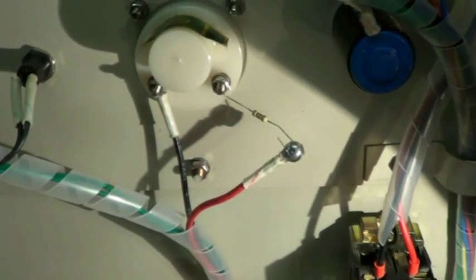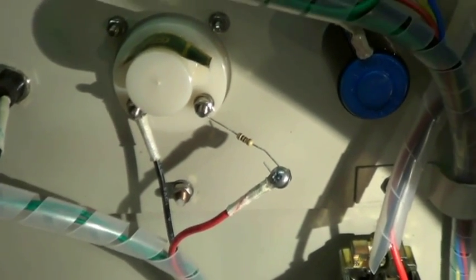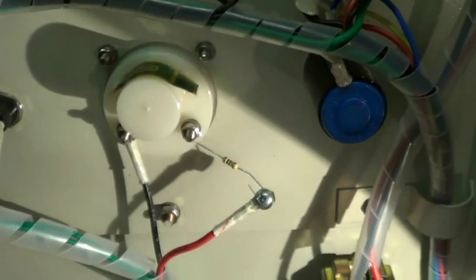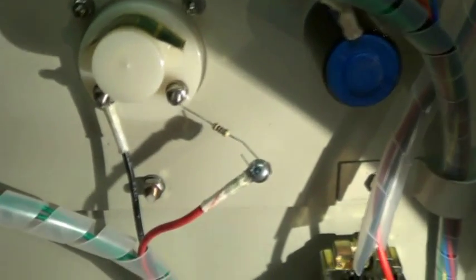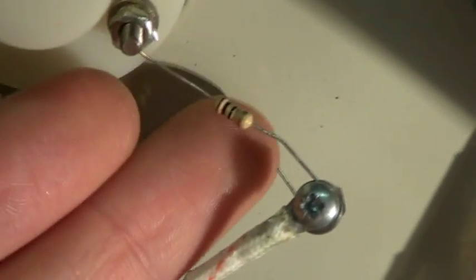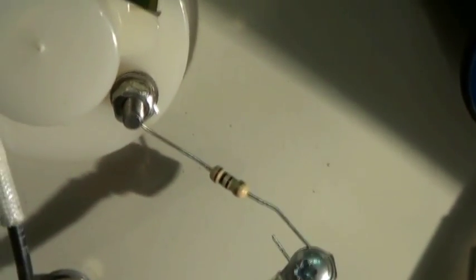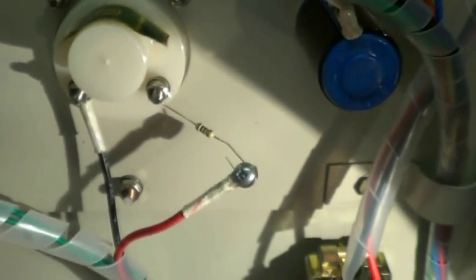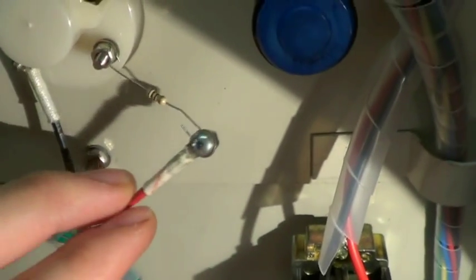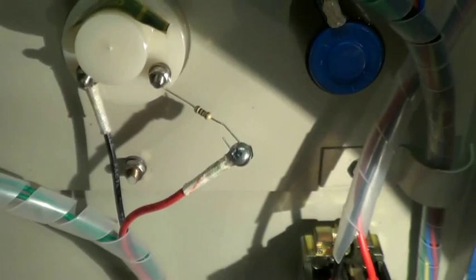To sense the current rather than putting the meter in series with the current path, I've added a 10 ohm resistor in series with the meter because it's up in the panel and easier to access. So I can simply measure the voltage across this to get the current.